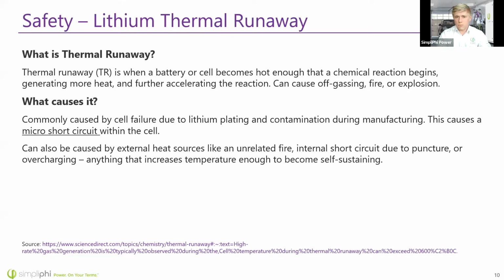So if you just light your lithium battery on fire, yes, it's going to go into thermal runaway. Or if there's an internal short circuit within the battery, maybe it's been punctured with a nail or a screw, or maybe it's even been overcharged. So anything that's going to increase the temperature of the battery enough to set that reaction off, it's going to then become self-sustaining.